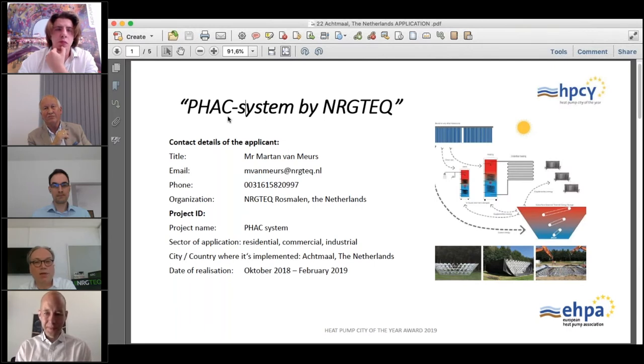With this system, we provide both the heat energy, but also the electricity. In fact, because there's no direct connection between heating hours and heating capacity, but it's more about how many solar hours you have available in summertime, and of course your cooling capacity, we can design the heat pump on the cooling capacity and run a lot of hours during summertime to collect all the heat needed for heating in the wintertime.